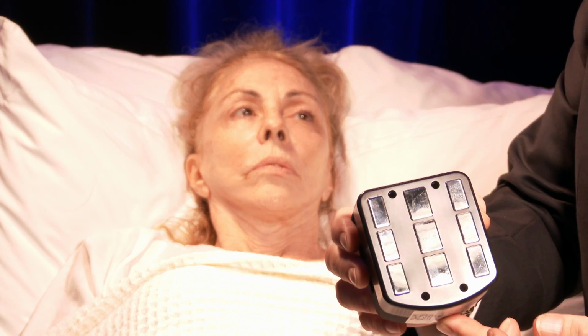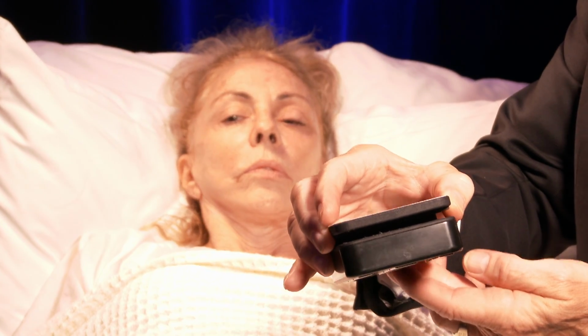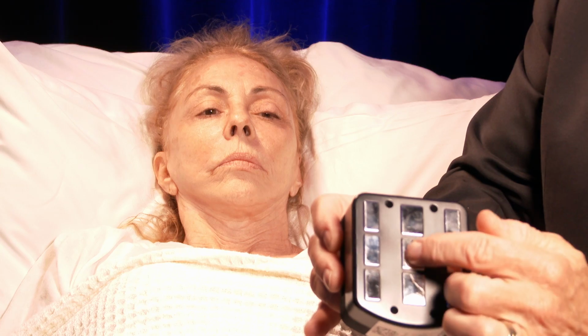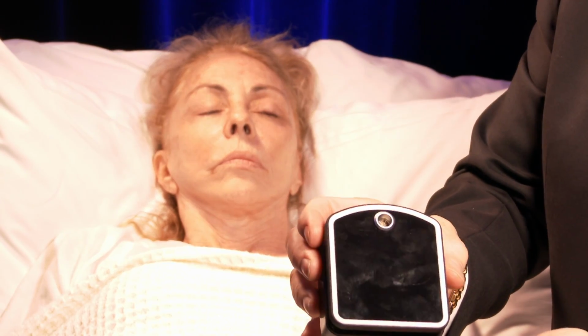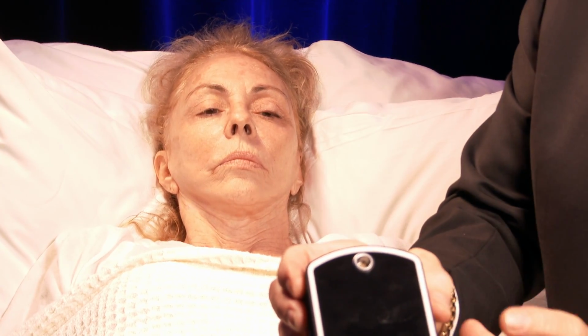So inside this applicator are built 9 different sensors that are sensing contact, high and low impedance, rate of rise of temperature, and the absolute temperature that you set. Each one of these 9 locations corresponds to one of the electrodes and corresponds to 9 dots on the surface of the applicator, so you can track and see where your temperature endpoint is at. Exquisite thermal control, which you'd expect from the BodyTite company.